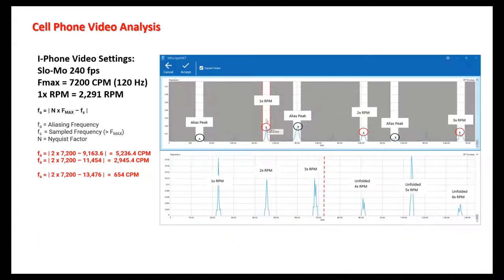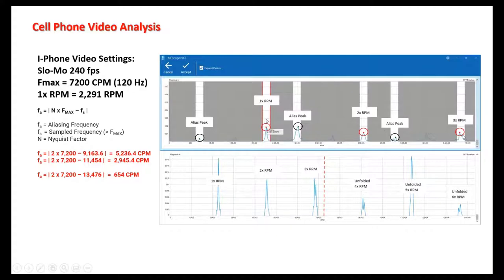In the software — same iPhone setup at 240 fps, fan speed 2,291 RPM — I found a 654 CPM aliasing frequency that was really low-level in the noise floor. What's nice is you move the cursor to the peak you're interested in — this is turning speed at 2,291 — and it shows you the harmonics at two and three times, and it shows where the aliasing peaks are calculated to be. You don't have to manually calculate anything. The software picks these peaks out for you.